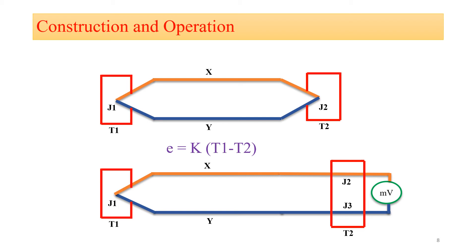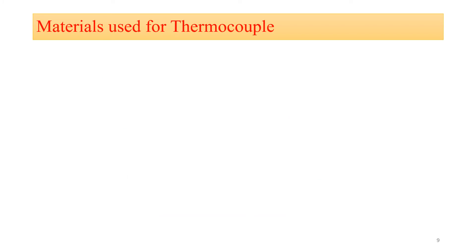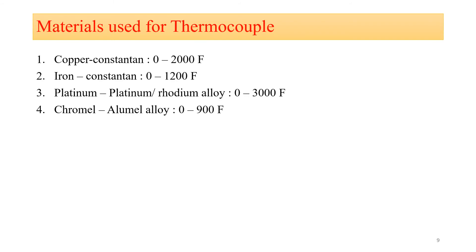A millivoltmeter is used to measure the thermally generated EMF. The thermocouple elements are enclosed in a housing assembly for protection, and the assembly is called a thermocouple probe. The different material combinations used for construction are: copper-constantan (temperature range 0–2000°F), iron-constantan (0–1200°F), platinum and platinum-rhodium alloy (0–3000°F), and chromel-alumel alloy (0–900°F).